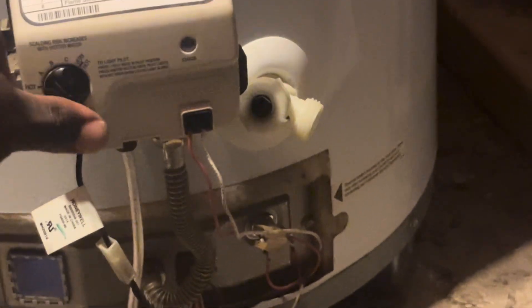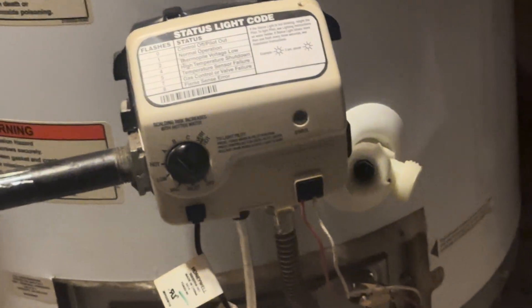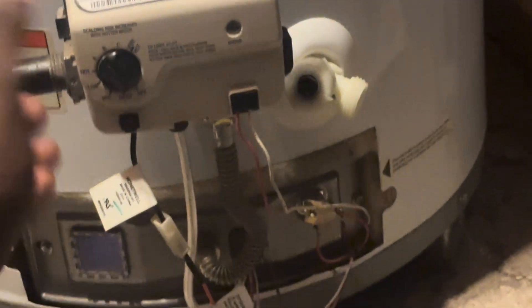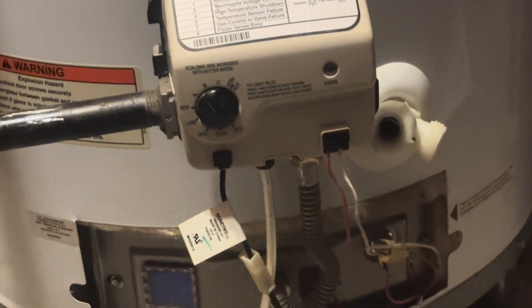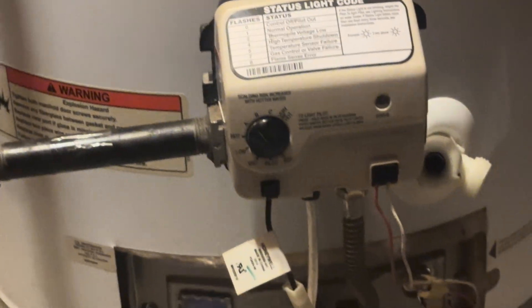Once you've waited 10 minutes and you don't smell any gas, turn the switch to pilot. When on pilot, you can push the switch in, which allows a small amount of gas in. You hold the switch in while pushing the igniter button — the igniter sends a small electrical shock down the wire. This unit generates its own small electricity using the thermopile to ignite the flame.